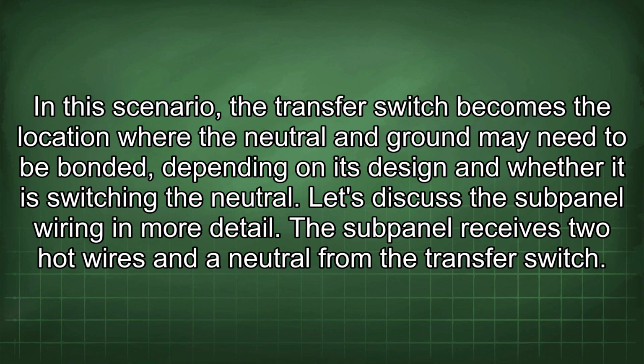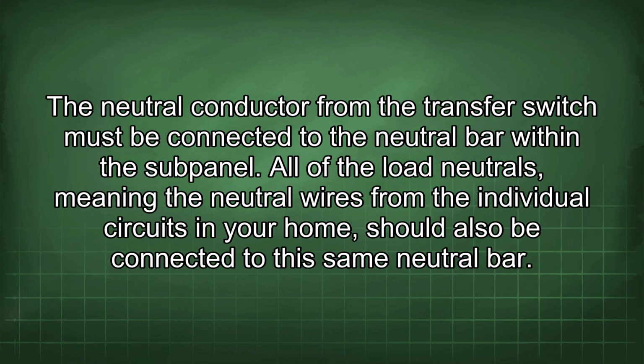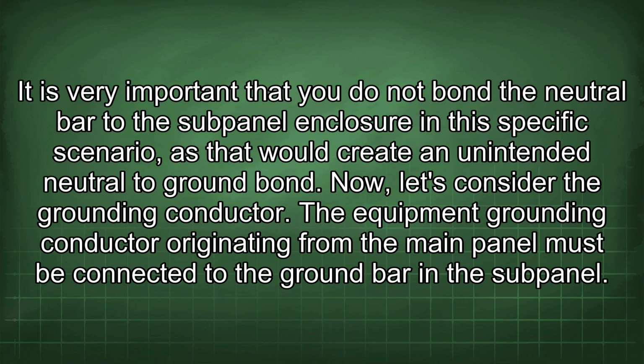Let's discuss the subpanel wiring in more detail. The subpanel receives two hot wires and a neutral from the transfer switch. The neutral conductor from the transfer switch must be connected to the neutral bar within the subpanel. All of the load neutrals, meaning the neutral wires from the individual circuits in your home, should also be connected to the same neutral bar. It is very important that you do not bond the neutral bar to the subpanel enclosure in this specific scenario, as that would create an unintended neutral to ground bond.